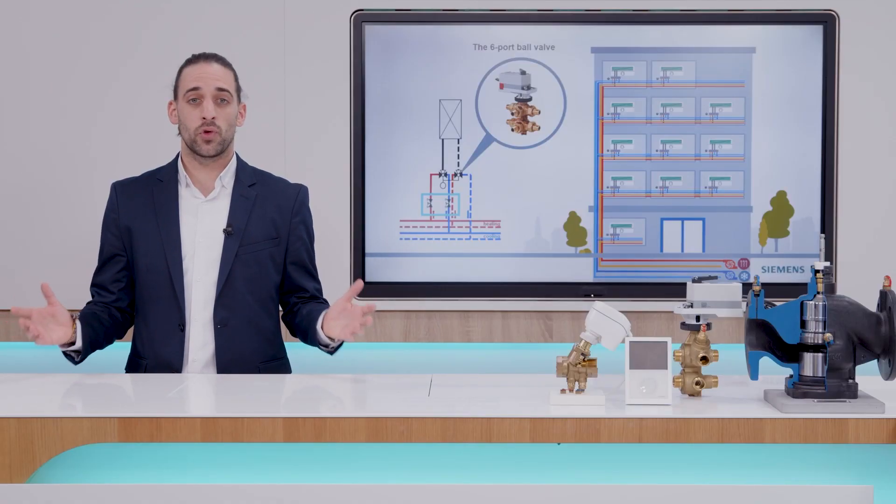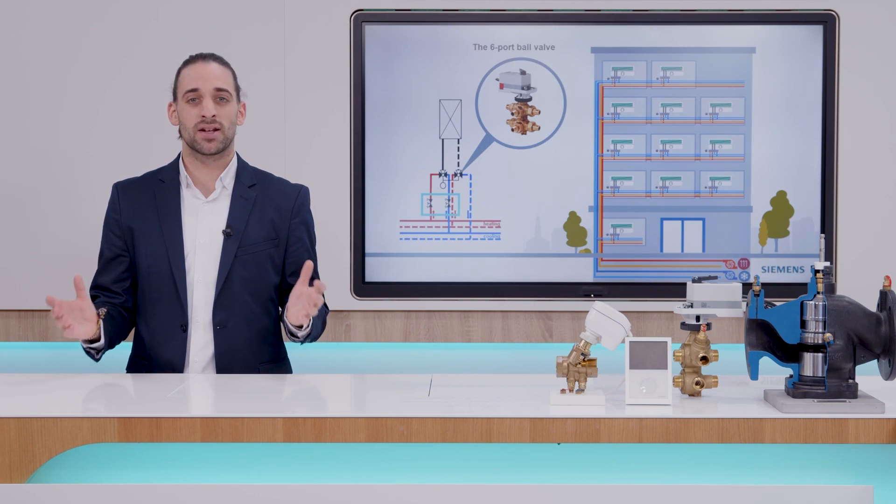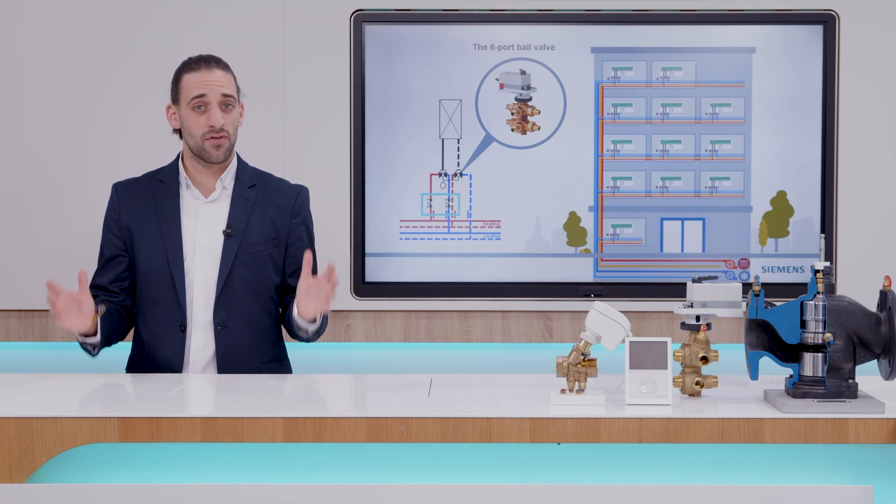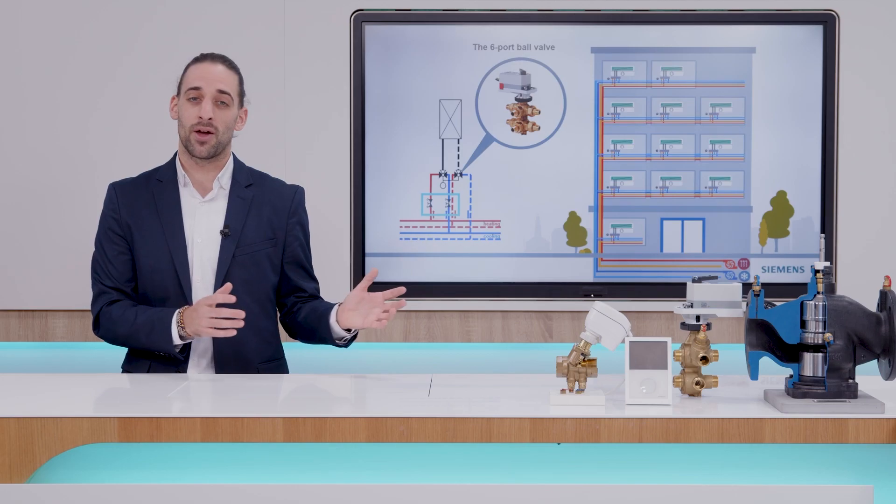On the other hand, those devices are still manual balancing valves, something you should definitely improve, as you already know from prior episodes. But in order for you to have the system dynamically hydronic balanced, PICV technology must be added.